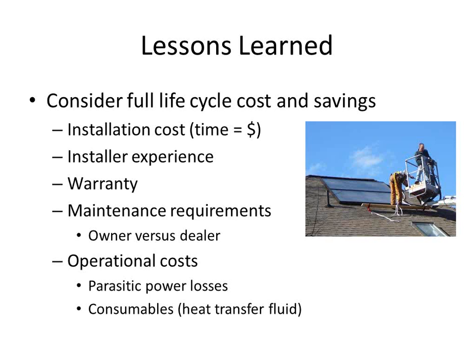If you've got a system with very large pipes to run the fluid back and forth, it's going to use a lot more glycol, maybe 5 or 6 gallons. Systems with very small pipes use a lot less. So that's something to factor in: are you going to have a $200 or $300 expense every couple of years changing out glycol, or a $50 expense every 10 years? That's something to look at.